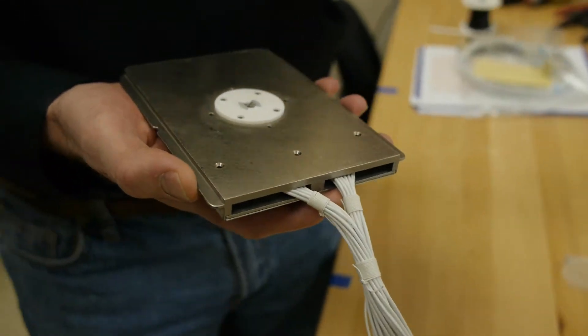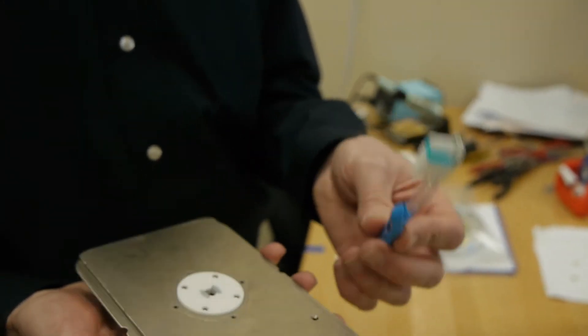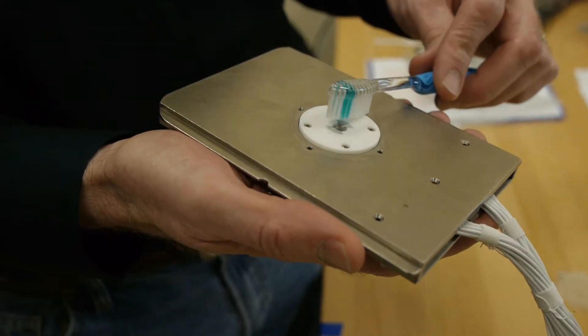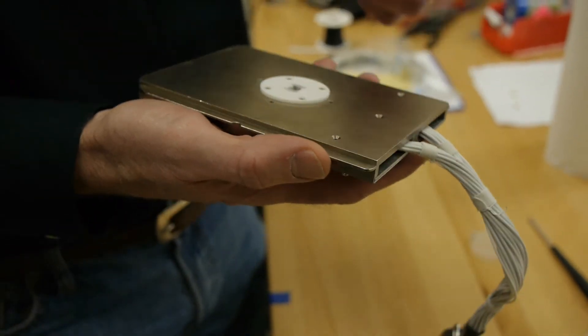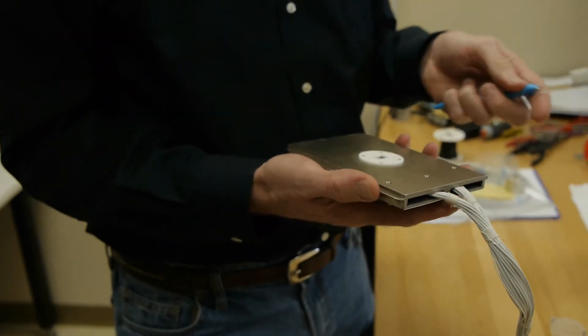A lot of you are afraid of using the toothbrush to clean particulate or clean the ceramics so that you get good high performance with the probe card. But it's very simple and very easy to use. You just use the toothbrush to clean off the ceramic, clean off any particulate. When you're probing a lot, you're going to get stuff on the probes, so you want to keep it clean.